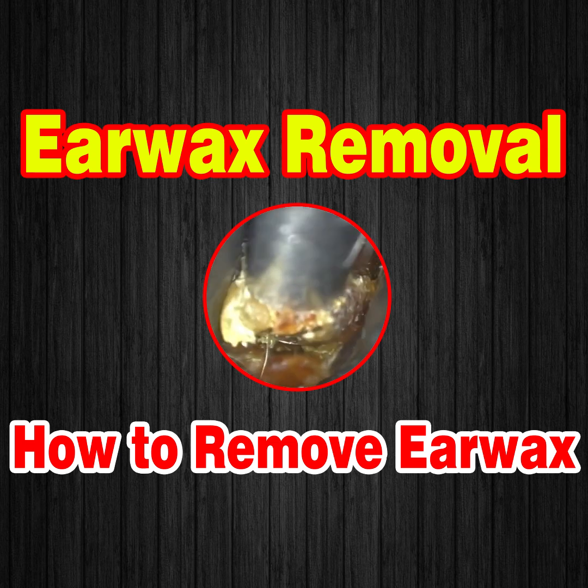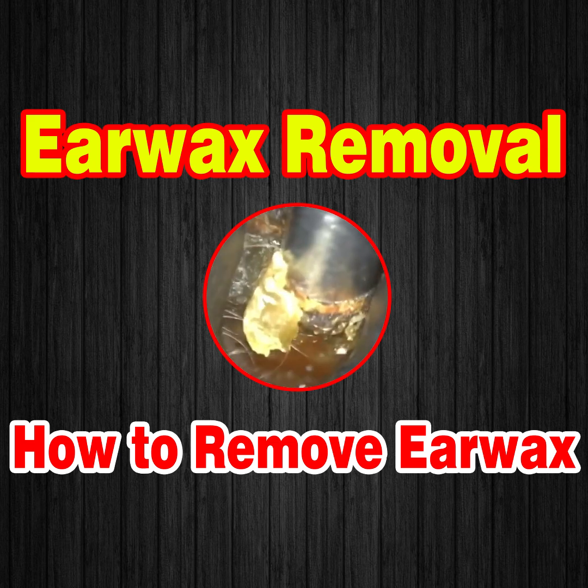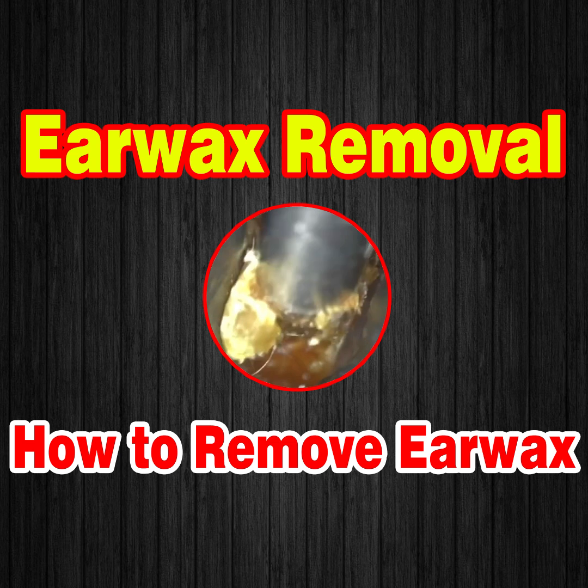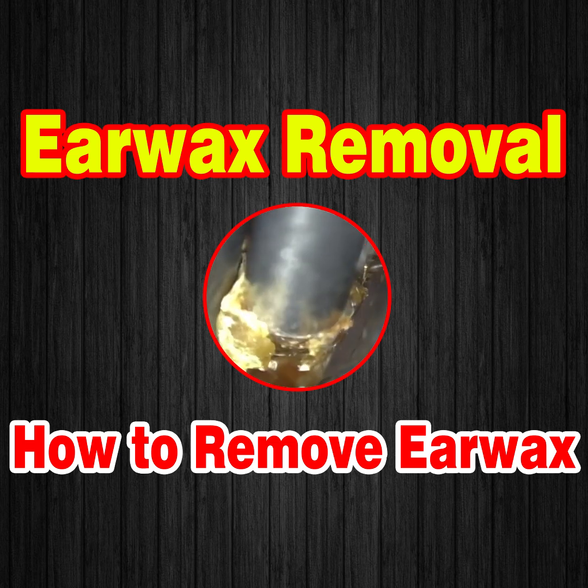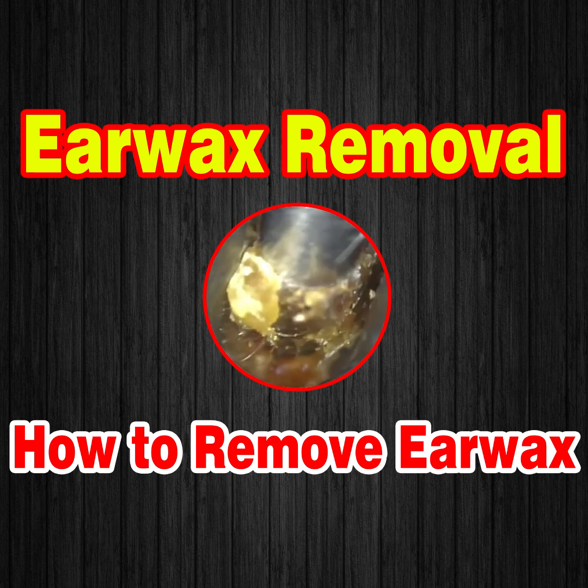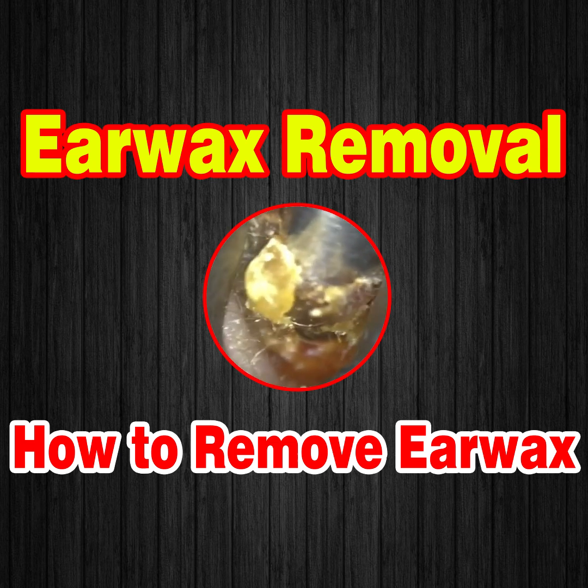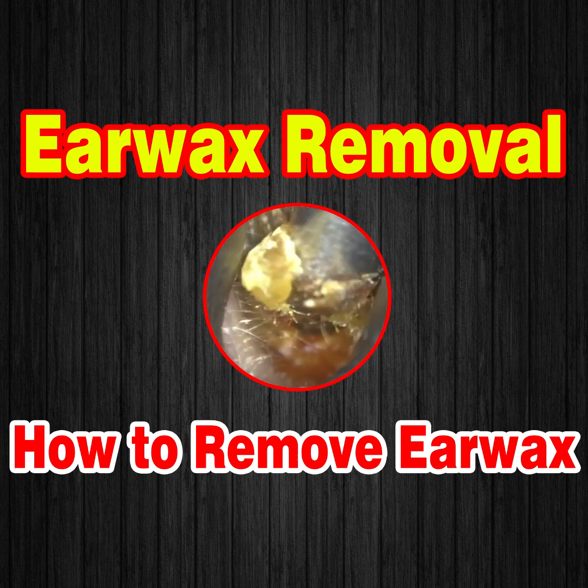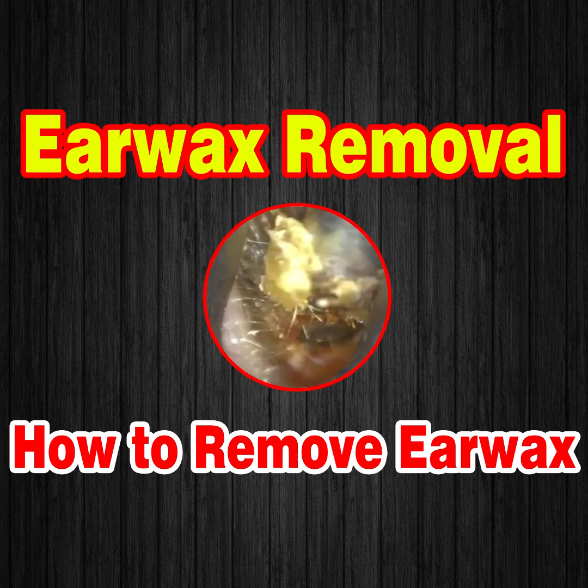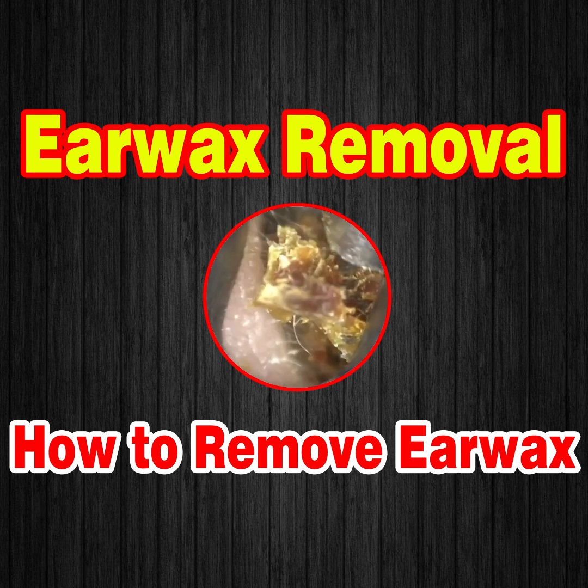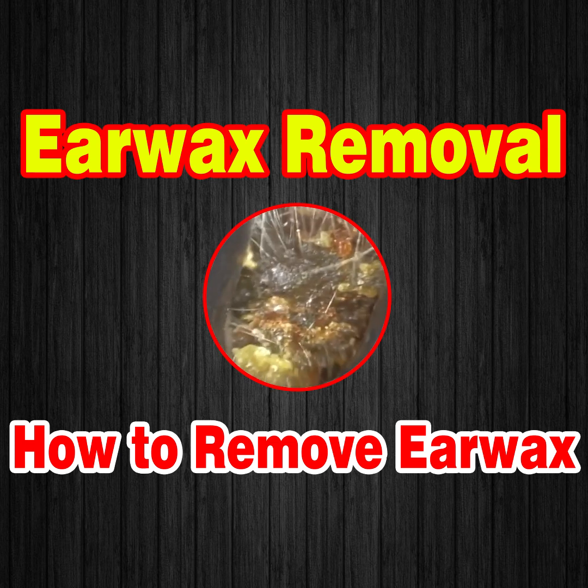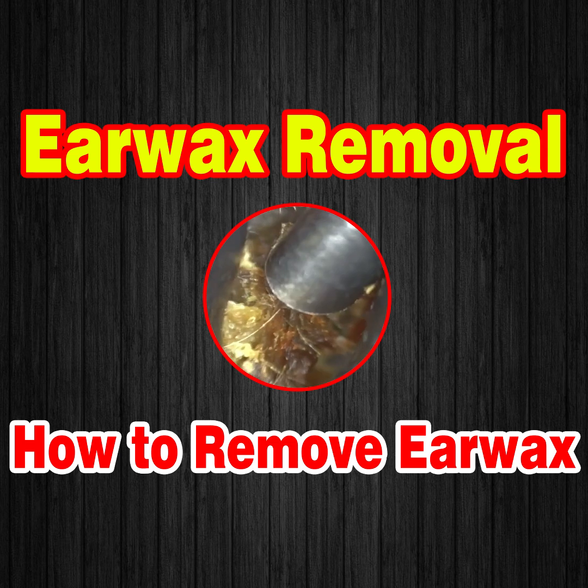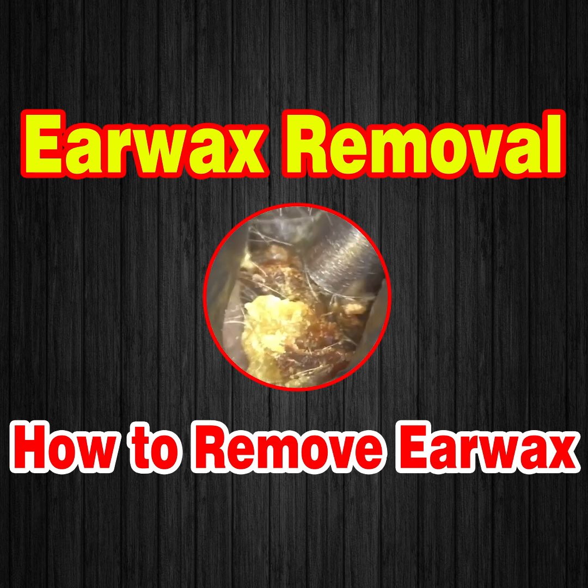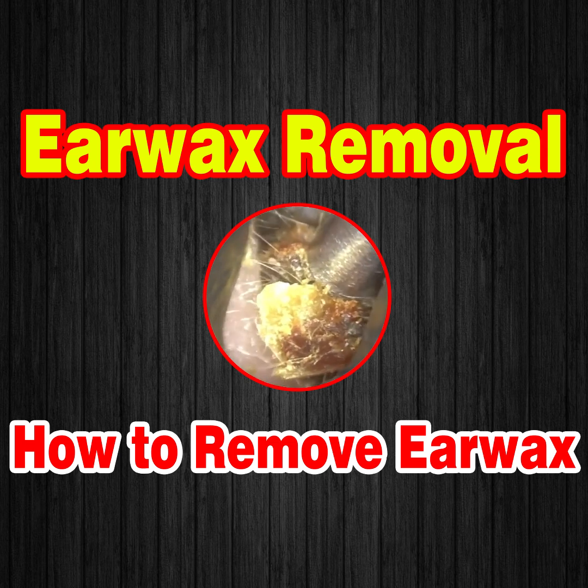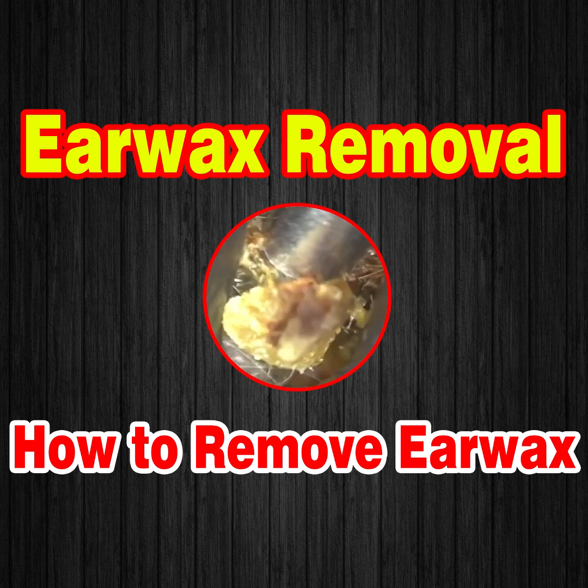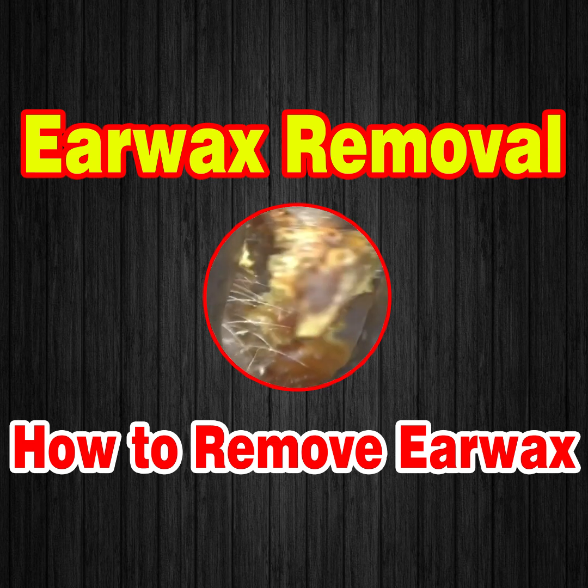What that enables us to do is not only provide better optics, because the instrument is not being inserted in direct line of sight of the camera lens, the WAXscope lens. If it was, you'd be seeing all the back part of the instrument, which then blurs the view. Because we're coming from a higher angle, the instrument is coming from top to bottom, so you're only viewing the tip of the instrument, and it doesn't blur the view. But also that slit provides a lot more manoeuvrability. So we're able to wriggle this wax a lot more than we normally would with the 3.5mm speculum, and it allows us to go further in the ear if need be.